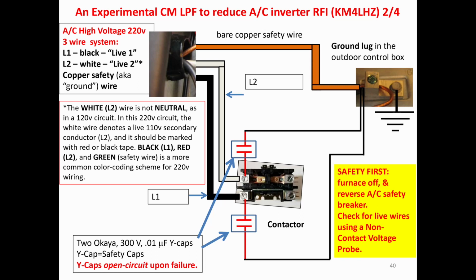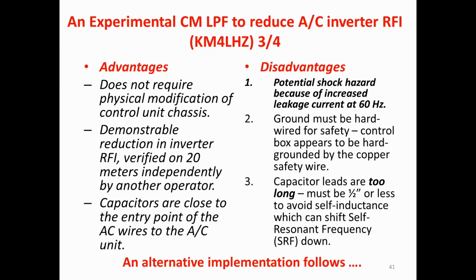But I took my two Y caps, I connected each to a terminal on the contactor, and I connected the other end to a ground lug, which is in the outdoor control board. Rather, it's in a control board in the outdoor unit after you open up the cabinet. These caps open circuit on failure, so they aren't going to destroy anything if they fail. It worked pretty well, and I'll show you that.